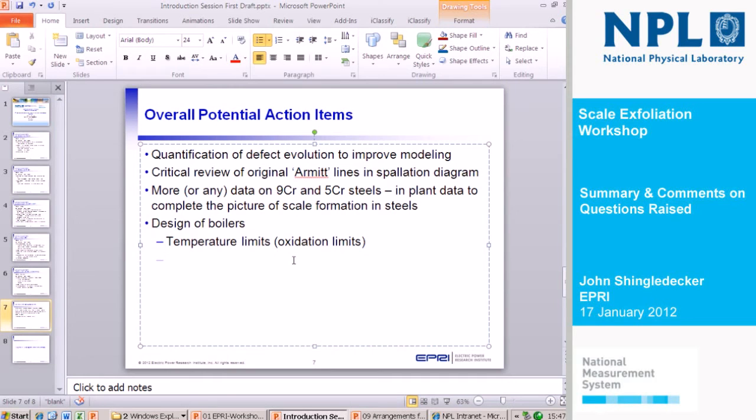Now, the two cases that he mentioned were a little foolish because they fill the thing with water, and then you would expect it, but I think I heard him say that there wasn't one. There was. The reason that it's important is because I work with utilities putting in new supercritical units, and we've just gone through a whole process in South Africa for 12 new 800 megawatt supercritical units, and we purposely designed them with horizontal surfaces because all the horizontal surfaces in Canada, for instance, have never had a problem, have never had an exfoliation problem.